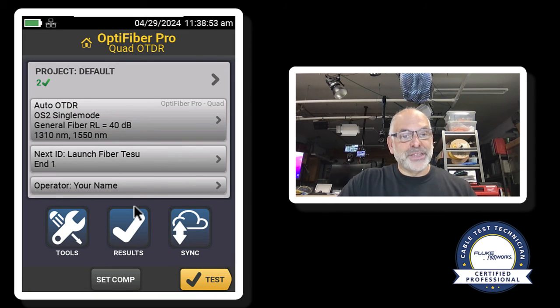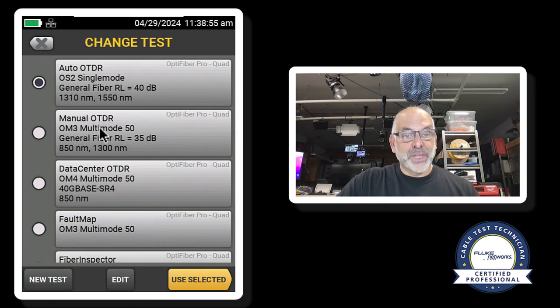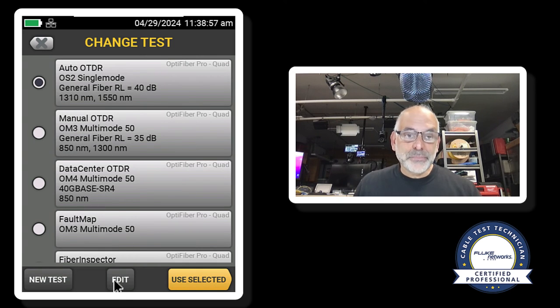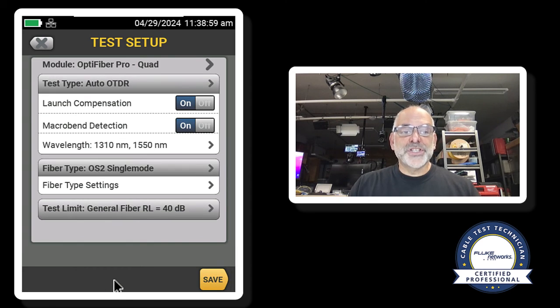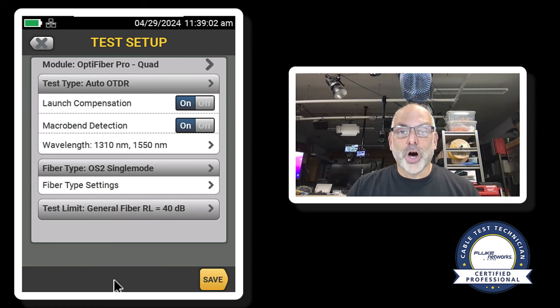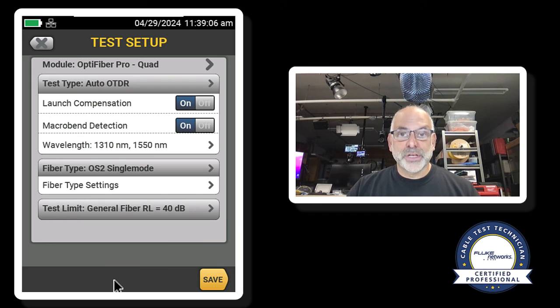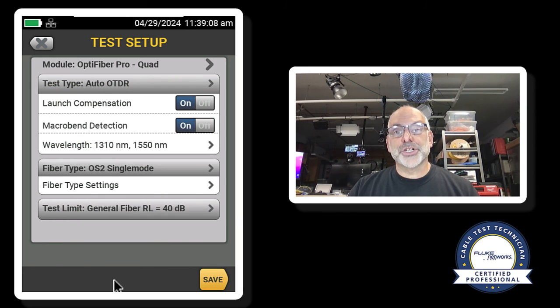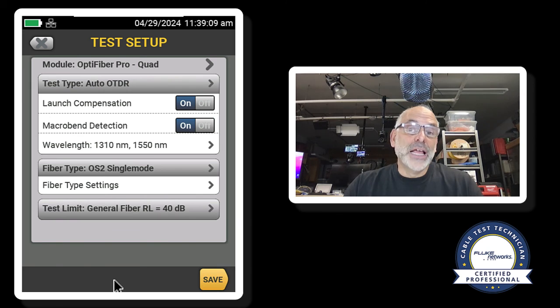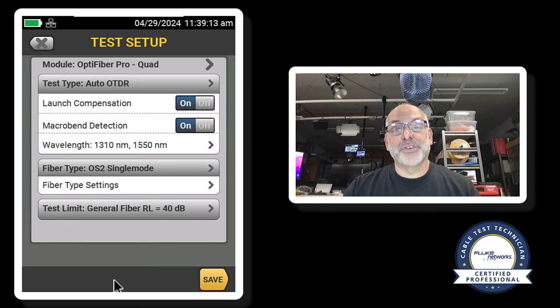Now here's the interesting thing. When I come into my test and I hit edit, we see that launch compensation is now turned on. So what this is telling me is that it will take into account I have a launch and a tail fiber and it won't include those in the length and the loss measurements for the fiber I'm testing.